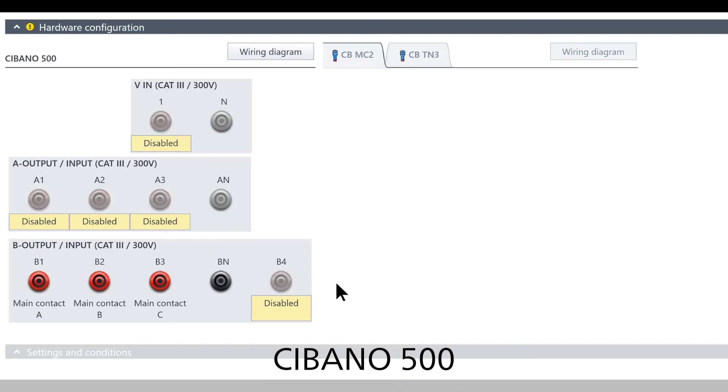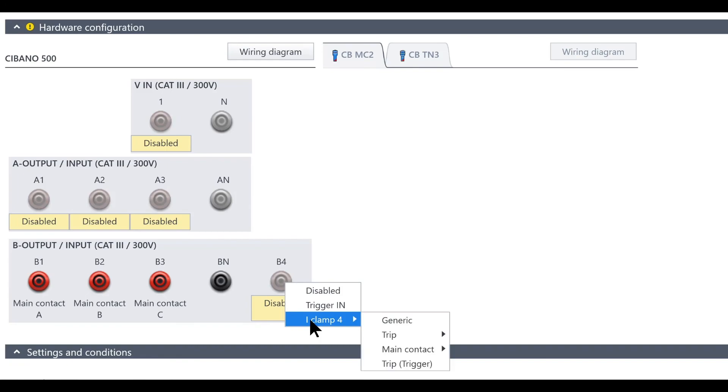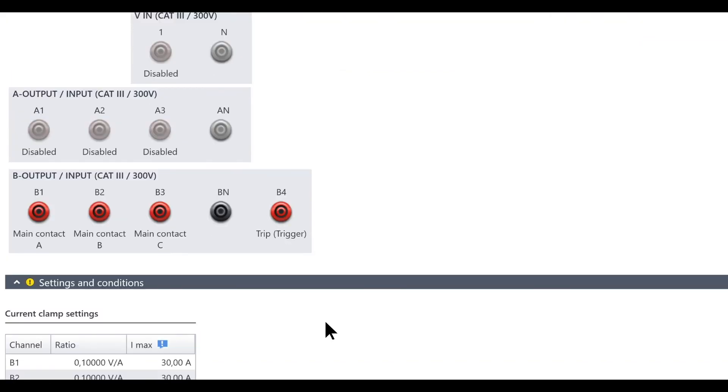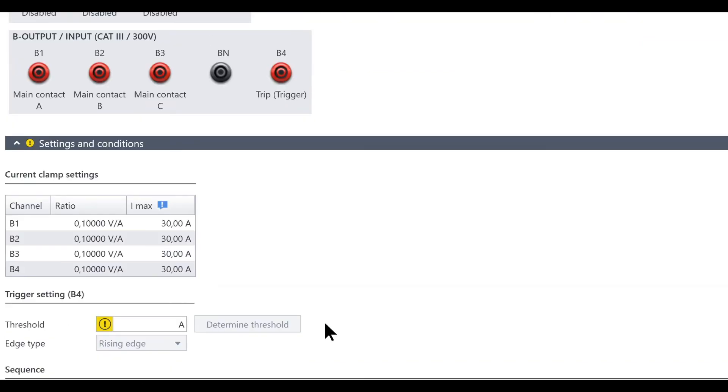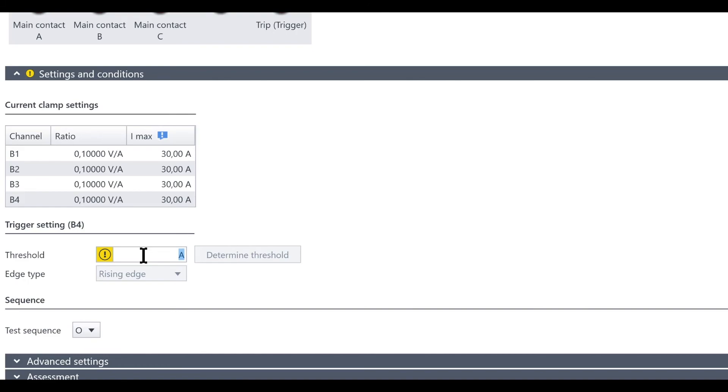With deactivated open loop check the power factor and capacitance tests can be performed without any error messages. For the CIBANO 500 we implemented a new trigger option in the first trip test. In the B-Row connections B4 can now be configured as a current clamp trigger. The only thing left to do before doing the test is to set the trigger threshold.